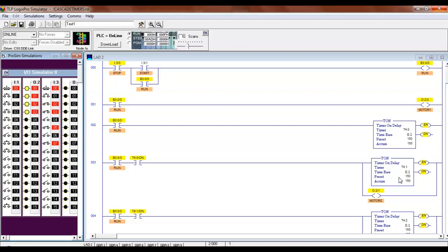So there's 4 motors. Sequence started 15 seconds after each motor. So this is what we use cascade timers for. What it does is it allows us to exceed just the 32,767 seconds that we're limited to on these guys. And it also allows us to sequence start something. Here I set them the same. They don't even have to be set the same, right? You understand?